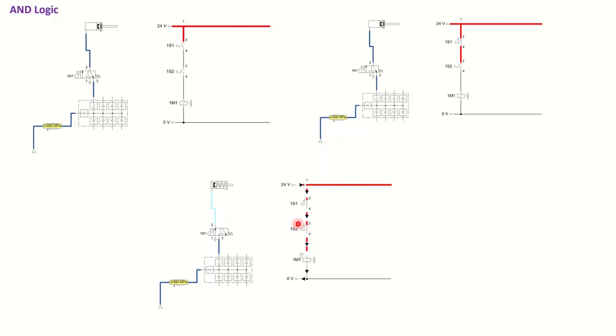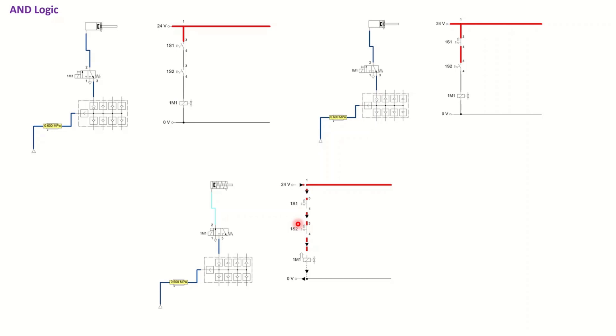If you look at twin pressure valve, it has kind of the same functionality — the same sort of principle. Twin pressure valve has two inlets and one outlet. Whenever we have air from both inlets, the system can provide air for the outlet. The same kind of thing is happening here because if 1S1 and 1S2 are in the ON condition at the same time, the system can operate and 1M1 will be energized. Also, if you watched the video on twin pressure valve, you can see we can use directional control valves in series in order to have AND logic — for instance a 3/2 directional control valve that we manually actuate, with both of them in series.